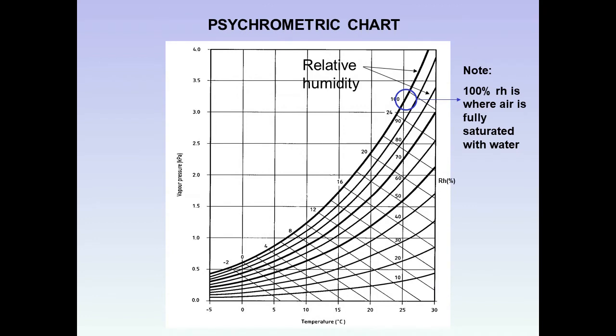When we've got our temperature and relative humidity, we could use a psychrometric chart to work out the dew point. And here's a psychrometric chart. Note that 100% relative humidity is where the air is fully saturated with water. The lines running from top right to bottom left are lines of relative humidity.